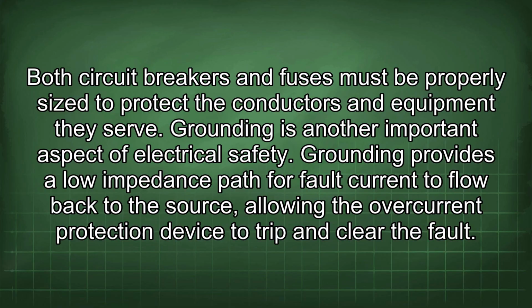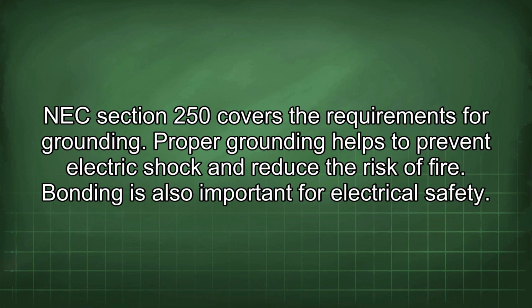Grounding provides a low impedance path for fault current to flow back to the source, allowing the overcurrent protection device to trip and clear the fault. NEC Section 250 covers the requirements for grounding. Proper grounding helps to prevent electric shock and reduce the risk of fire.